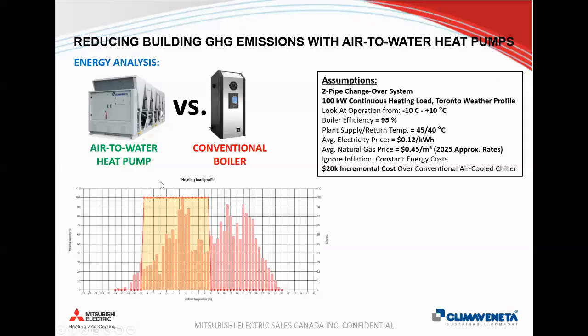So we're only analyzing between -10 and +10. Below -10, the auxiliary boiler works anyway, so it doesn't matter. And in a two-pipe changeover system, you will get higher efficiencies if you are doing heating between 10 and 20 degrees Celsius, but not to skew the results, I just looked at -10 to +10.